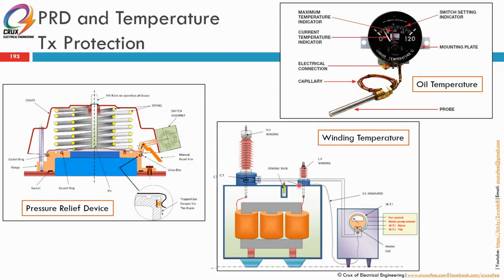While the winding temperature is also using the same concept as the oil temperature, there is an additional heating coming from the CT. So the CT is measuring the normal current of the load. This current will be used to heat up another heater element, which will increase the temperature reading of the temperature indicator. So normally the temperature reading difference between the winding and the oil is about 5 degrees Celsius. Alright, so in this case, normally if it's a paper insulated, the alarm is set at 95 and the trip is set at 105 degrees Celsius.